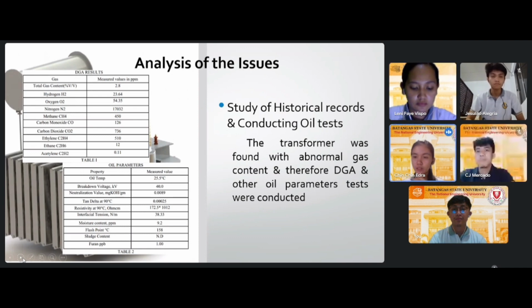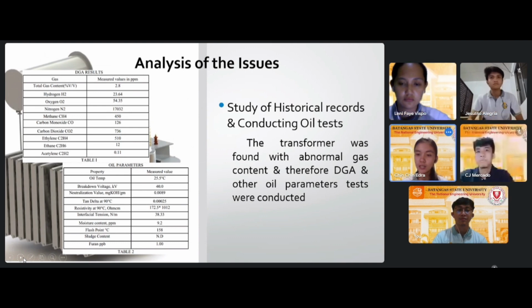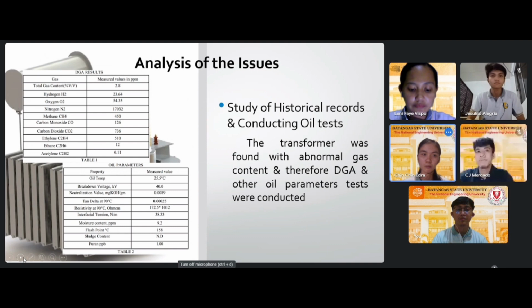Analysis of the issues. The first step of analysis is to study the historical record and conduct oil tests. The first analysis was done through dissolved gas analysis, or DGA, which enables us to get the total gas content of the power transformer. Next, an oil test was also done to get each parameter needed for the analysis. After the tests were done, abnormal gases were detected according to the results of the test, which can be seen from the table.